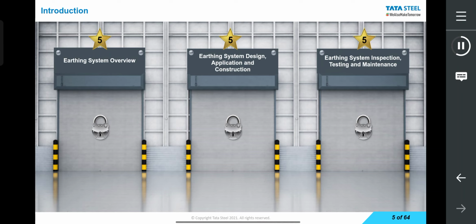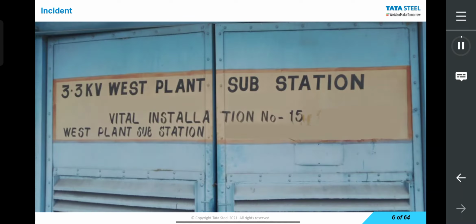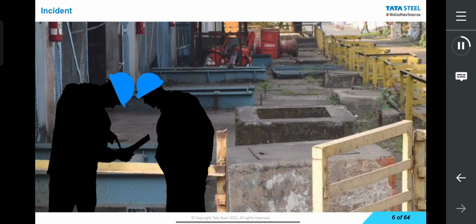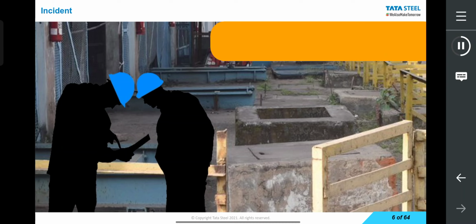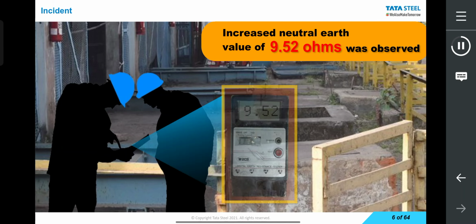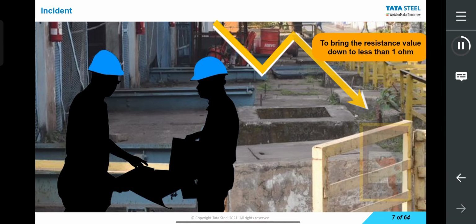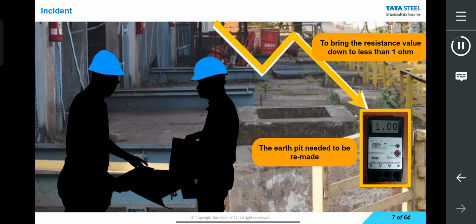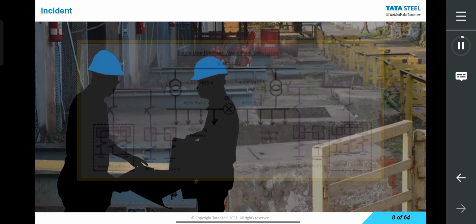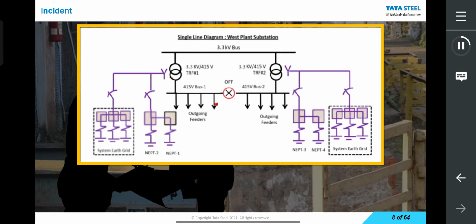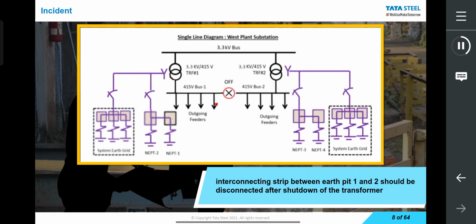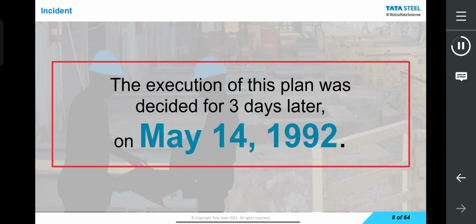Before you begin, let me share an incident that explains the importance of following safety norms for earthing system. On May 11, 1992, the electrical engineer at West Plant Substation reported an increased neutral earth value of 9.52 ohms for transformer 1 to his superior. To bring the resistance value down to less than 1 ohm, the earth pit needed to be remade. They checked the single line diagram of this bus and decided that before starting the digging job, the interconnecting strip between earth pit 1 and 2 should be disconnected after shutdown of the transformer. The execution of this plan was decided for 3 days later, on May 14, 1992.